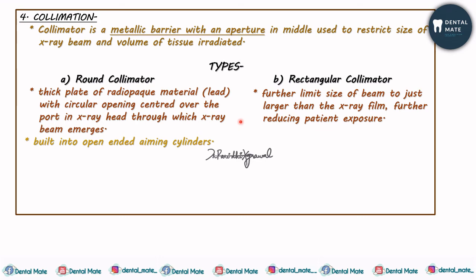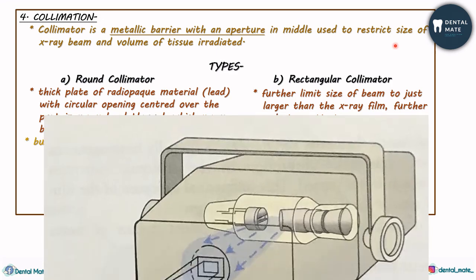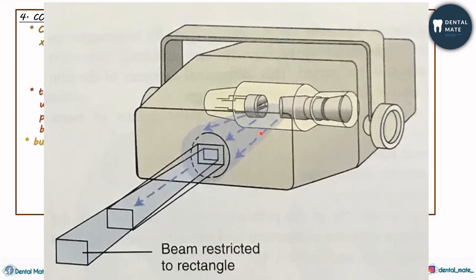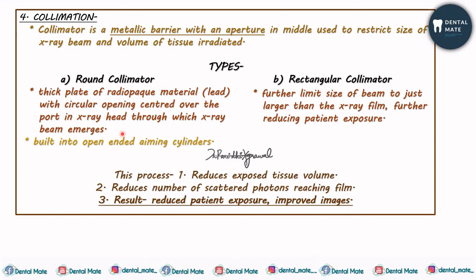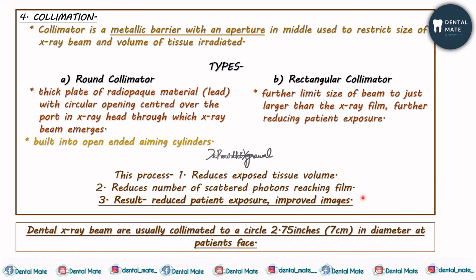With the rectangular collimator, the beam is restricted to a rectangle. Collimation reduces the exposed tissue volume and reduces the number of scattered photons that reach the film, because photons pass through the collimator aperture. The result is reduced patient exposure and improved image quality. Dental x-ray beams are usually collimated to a circle of 2.75 inches — approximately 7 cm — in diameter at the patient's face.